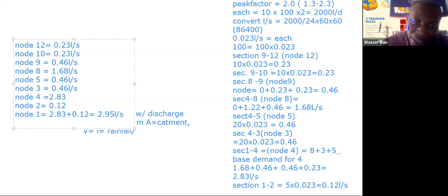And those pipes are 0.12 and 100. So from what I said yesterday, if you get 2 values, you use the bigger one. So this is my 3 and this is my 1. It's falling between 2 and it's falling almost on this line of 0.3. So the velocity is okay and the pipe size is 125 mm. I've designed it. That is your design.